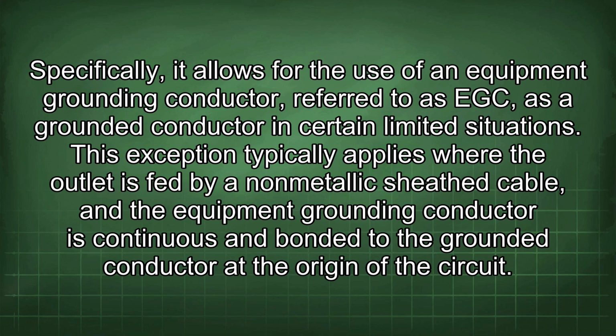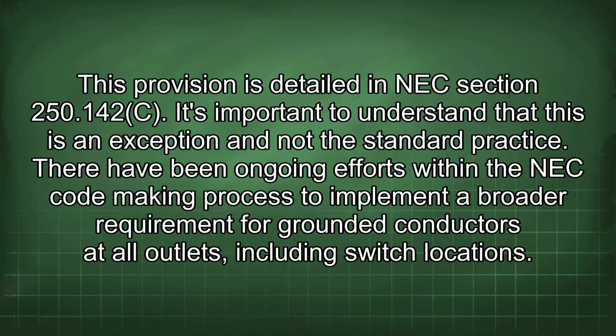Specifically, it allows for the use of an equipment grounding conductor, referred to as EGC, as a grounded conductor in certain limited situations. This exception typically applies where the outlet is fed by a non-metallic sheathed cable and the equipment grounding conductor is continuous and bonded to the grounded conductor at the origin of the circuit. This provision is detailed in NEC section 250.142c. It's important to understand that this is an exception and not the standard practice.